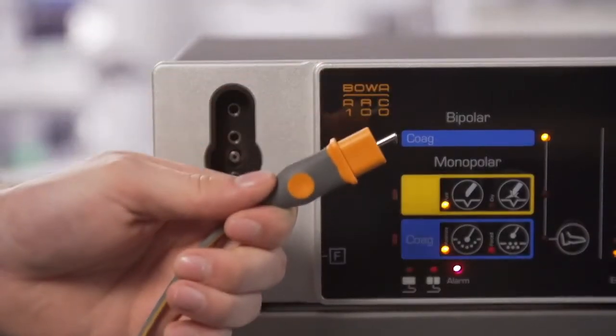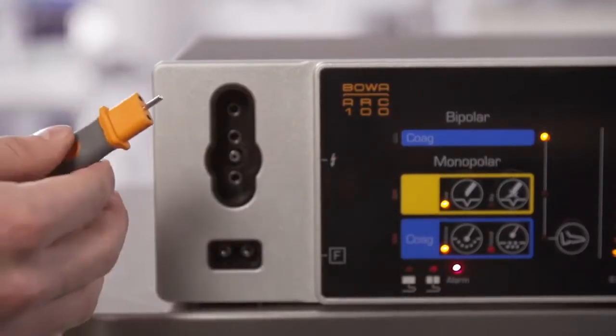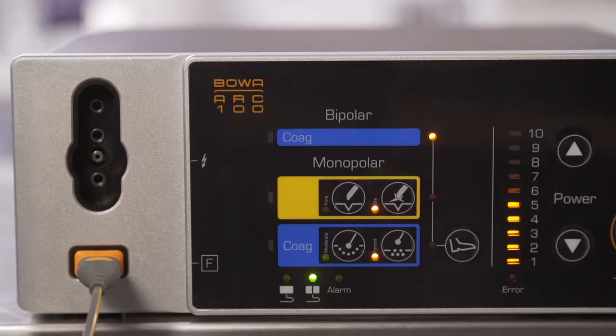Plug the neutral electrode cable into the ARC 100. The easy neutral electrode monitoring recognizes and automatically displays the type of neutral electrode used and indicates this with a green signal. The red LED identified by an alarm always shines when no neutral electrode is connected. In this case, monopolar activation is not possible. For the protection of patients, BOWA essentially recommends the use of split easy neutral electrodes, which can thus be monitored.